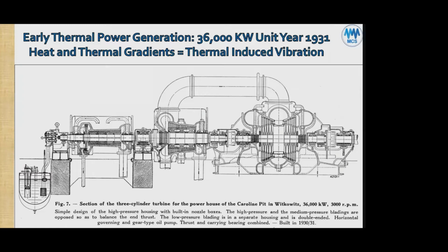As you can see, as high temperatures enter through the casing, through the steam entering in the casing, there will be deflections in the casings. They will not grow exactly perfectly well thermally. And the same with the rotor. It doesn't grow perfectly, especially at startup conditions, and even when it's warmed up, because there's hot steam entering, and this is going to impact with a higher temperature in some parts of the rotor, but at other parts of the rotor you have lower temperatures. Now we don't need exact uniform temperature from left to right on the turbine, but we do of course need a uniform temperature at each section to minimize thermally induced vibration.